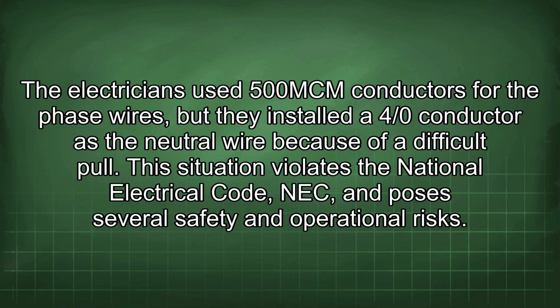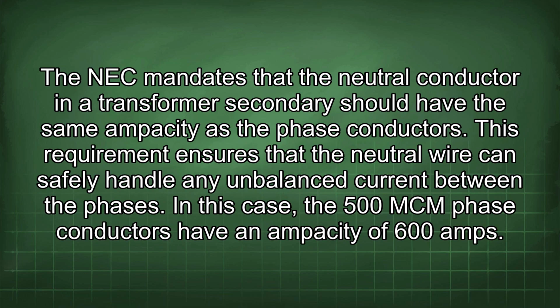This situation violates the National Electrical Code (NEC) and poses several safety and operational risks. The NEC mandates that the neutral conductor in a transformer secondary should have the same ampacity as the phase conductors. This requirement ensures that the neutral wire can safely handle any unbalanced current between the phases. In this case, the 500 MCM phase conductors have an ampacity of 600 amps.